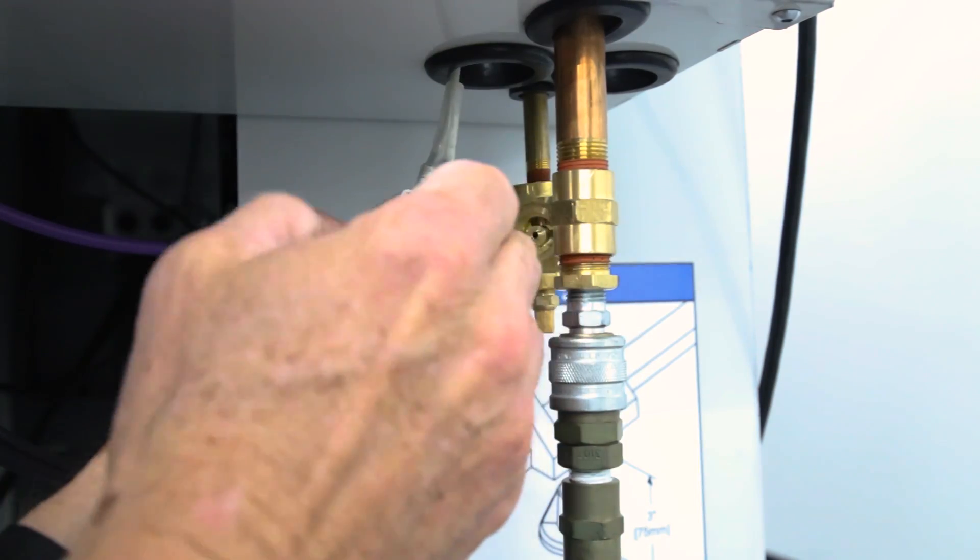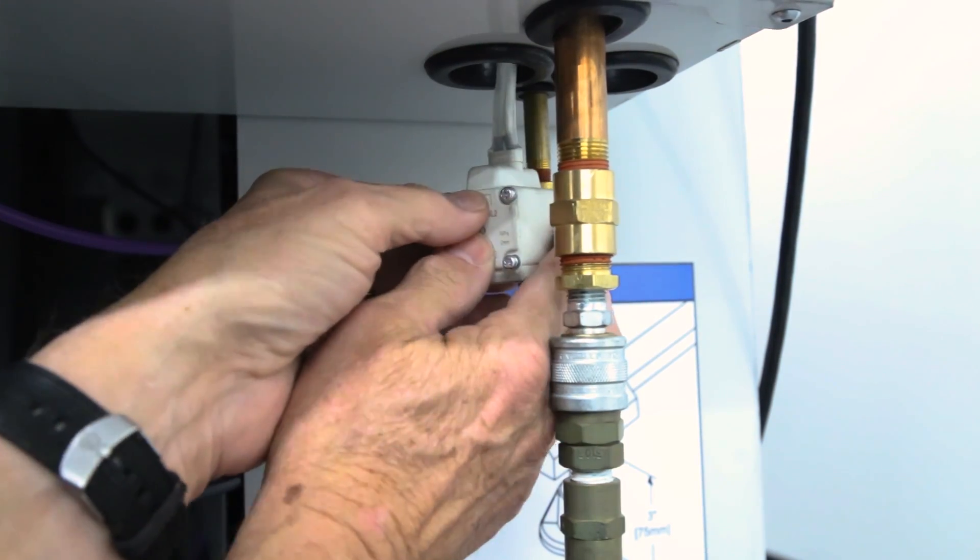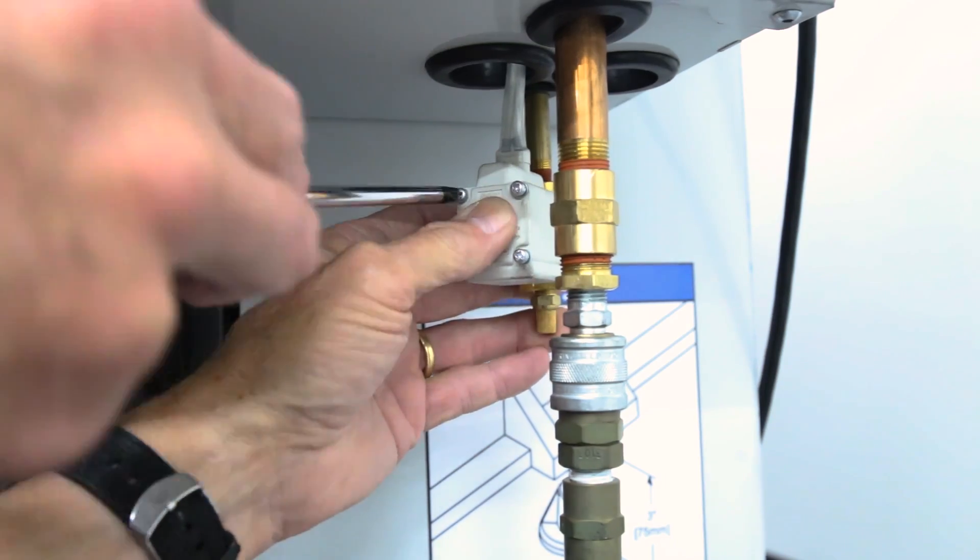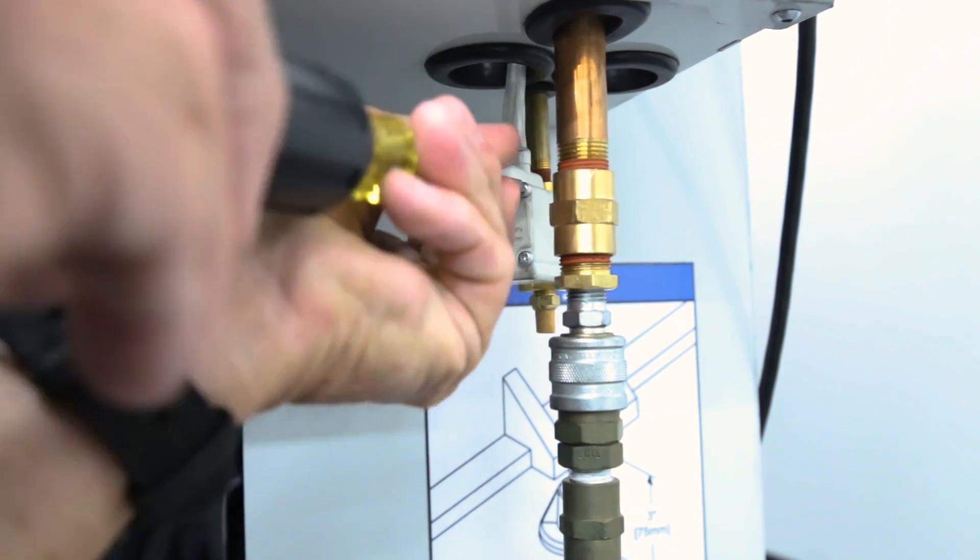Put the spring into the coil assembly. Put on the washer and push in the plunger. Put the coil assembly against the manifold. Put in the four screws and then tighten them in a star pattern. Tighten the screws until they're snug, but don't over-tighten them.